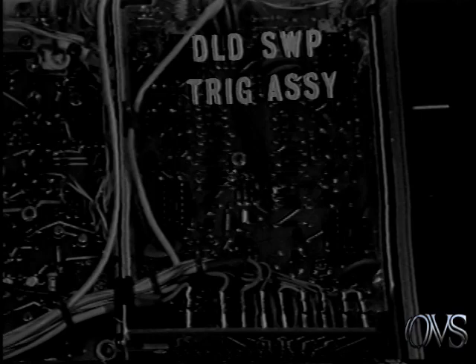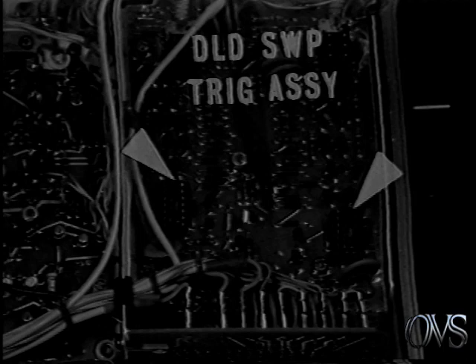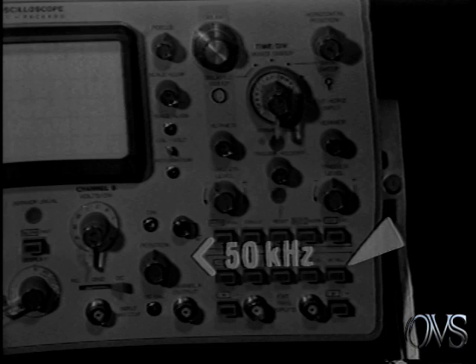In the trigger assembly for delayed sweep models, the main and delayed trigger integrated circuits are identical and may be interchanged to determine if one is defective. One final point: the 1700 trigger circuit is very sensitive and may trigger on system or high frequency noise on the input signal. Selecting high frequency reject improves triggering on noisy signals below 50 kilohertz.